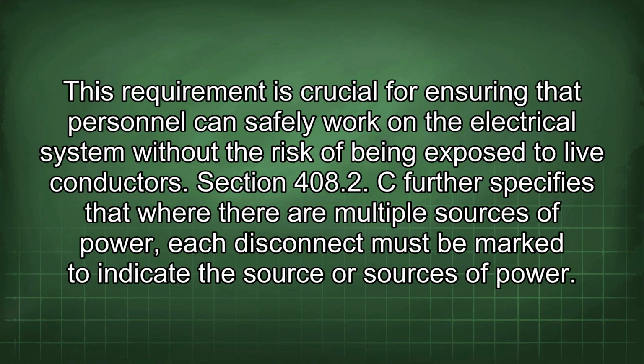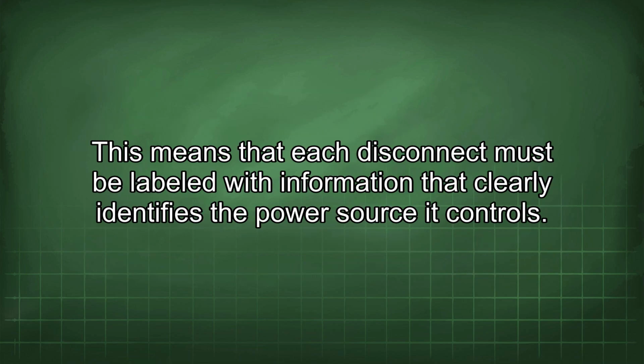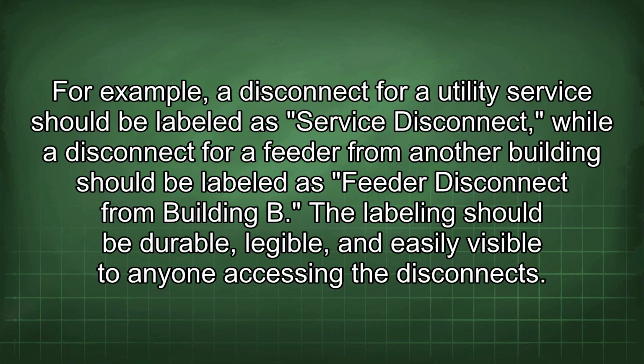This requirement is crucial for ensuring that personnel can safely work on the electrical system without the risk of being exposed to live conductors. Section 408.2 C further specifies that where there are multiple sources of power, each disconnect must be marked to indicate the source or sources of power. This means that each disconnect must be labeled with information that clearly identifies the power source it controls. For example, a disconnect for utility service should be labeled as service disconnect, while a disconnect for a feeder from another building should be labeled as feeder disconnect from building B.